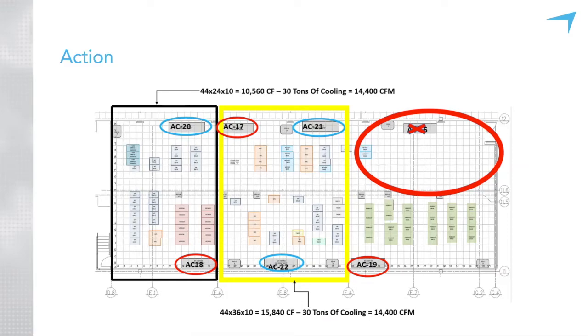Just very quickly, the data center footprint shrinks. At one point, that area was full. This one was easy, that CRAC unit was not cooling anything, so cycling it off became very easy. What this data center is doing is they alternate every 30 days: AC20's on, AC18's off, and vice versa.